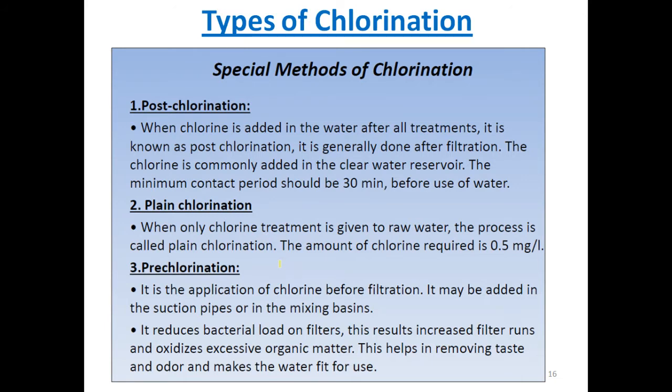Okay, now pre-chlorination. What is pre-chlorination? It is the application of chlorine to water before its treatment, especially before filtration. It may be added in suction pipes or in mixing basins. It reduces the bacterial load on filters. This results in increased filter runs and oxidizes excessive organic matter. This helps in removing taste and odor and makes the water fit for use.